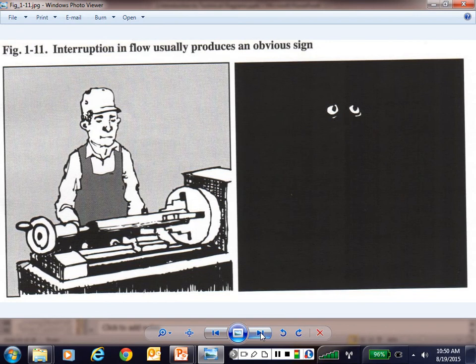One of the main things you do when you troubleshoot, the second thing on the list, is to look things over. Just look the system over, because a lot of times the problem is what? It's obvious. You've got a hydraulic pneumatic system, and you go out there and you've got a broken pipe, right? Or you've got hydraulic fluid all over the floor, or a blown fuse.